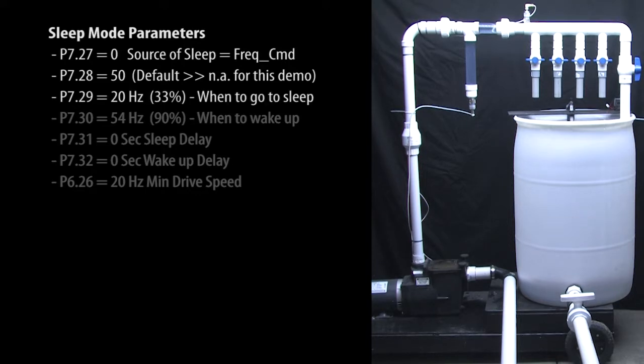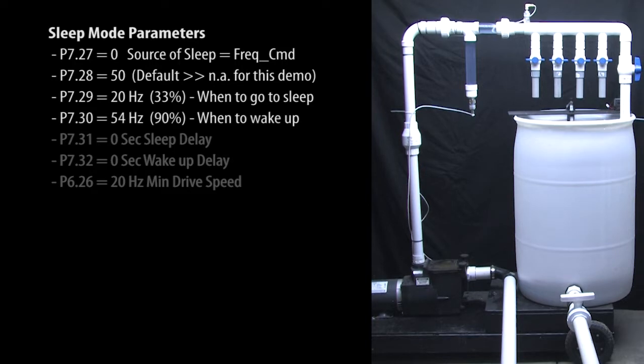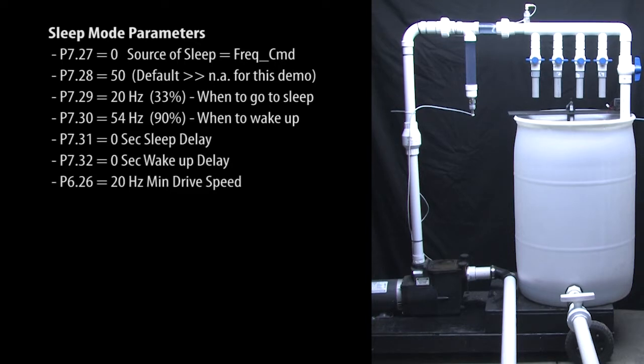This is the drive frequency where we want to turn the motor off or go to sleep and this is the drive frequency where we want the motor to wake up and start pumping again. I am going to set these parameters without explanation because it will be easier to understand them after we run the demo.